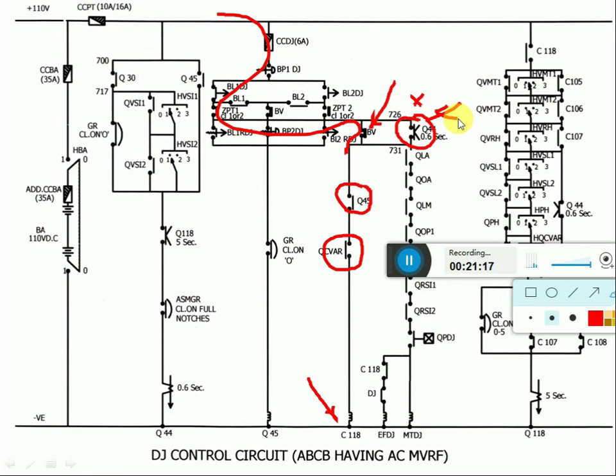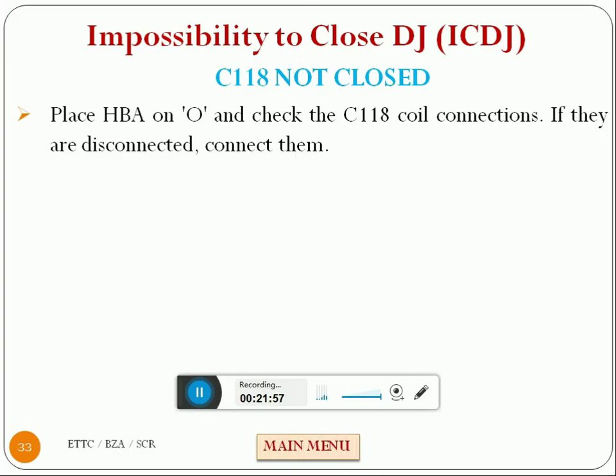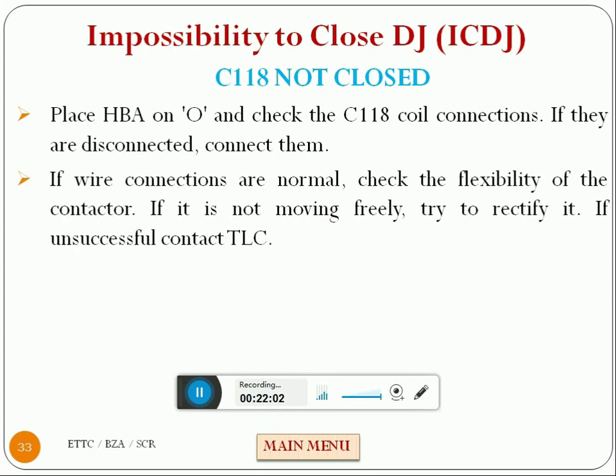If successful, work further. If not successful, or unable to attain, contact TLC for advice. We should not wait, or we should not operate manually, for the C118 coil. So if C118 is not closed, ensure the coil connections; if any is disconnected, connect with precautions by keeping it on 0. Check the flexibility of the contactor with precautions.